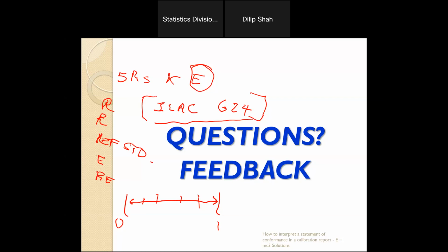Simple document. The other one is an NCSLI recommended practice, but it is more complex. It is a good document if you have thousands of artifacts of calibration, and it uses a very complex statistical approach of determining intervals. For example, the US Navy does that, but the US Navy has thousands of artifacts. One gentleman, who is retired from the Navy now, used to do that interval analysis, and if you said, I have this instrument model, what is the calibration interval for this?